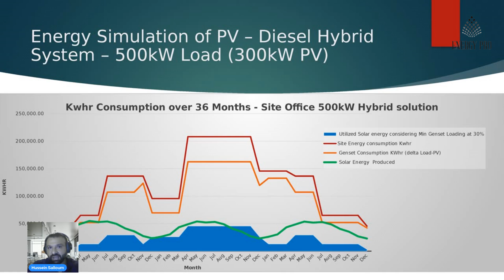So if you see over 3 years, the red line, the top line, is the total site energy consumption in kilowatt hours. With the hybrid solution, the PV and the generator, the generator consumption is the orange line. So you can see the major difference between the consumption of the generator alone and with the PV. That is due to the green line, the solar energy production. However, the green line, which is the solar energy produced, is not fully utilized because, as we said, during the day there should be a minimum of 30% utilization for the generator to keep the spinning reserve. So the actual saving is the blue area. The blue area constitutes the utilized solar energy saving during the generator operation. So this blue area is the diesel saving during 3 years of a 500 kilowatt project site.